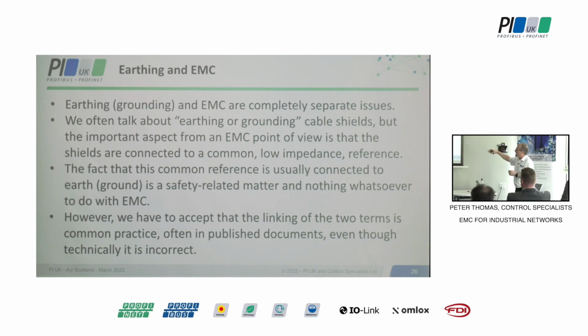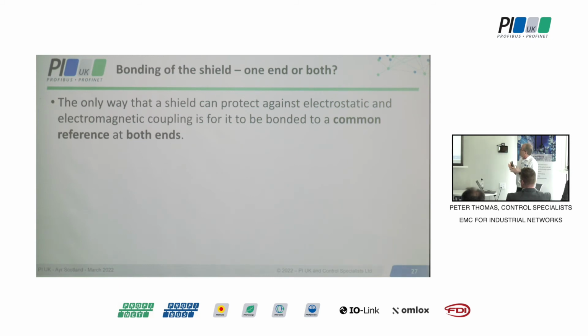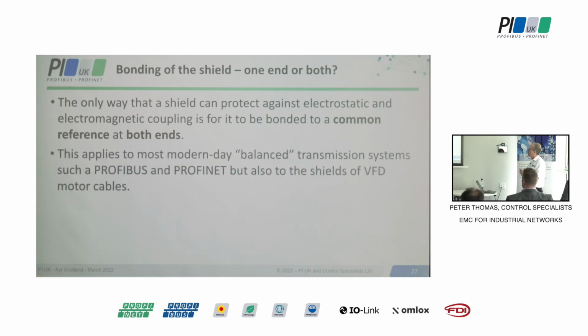We have to accept, though, that it is common practice. Grounding and earthing just still gets used. Right, this is the reality then. One end or both. Well, I was from the school of one end, and the vast majority of people, even nowadays, still seem to be one end. Now, it doesn't mean that they were wrong. What it means is a lot of the electrical circuits have changed, so it's no longer applicable. And what is for sure is that the only way a shield can protect you against both electrostatic and electromagnetic coupling is for the shield to be bonded to a common reference at both ends.